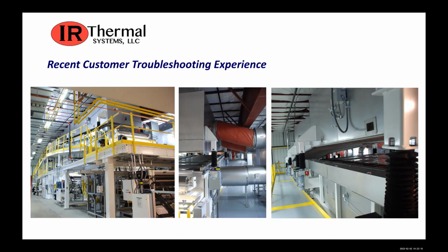I printed out the P&ID. We went out and sat down with the customer. They had already changed out all the pressure transmitters, and we started doing some experiments, raising and lowering velocity. And once again, we were unable to see why the top nozzle velocity was not operating in conjunction with the lower velocity. We'd raise the lower velocity, and the top velocity would just stay the same.